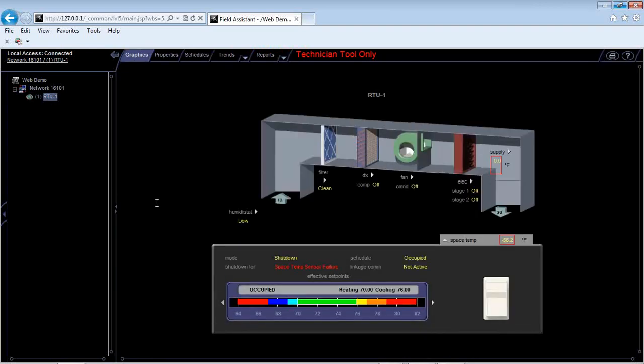Okay, so this is my view file. This is exactly what is going on with my controller, just kind of a general graphic status, right? So you can see I have a filter, a DX section, a fan, an electric heat exchanger, and then I've got some temperatures, okay? This is a brand new Carrier controller, okay? All of these rooftop controllers come standard with their RTU Open program on it. So all I did was upload this. I didn't add anything. I just hit upload, and this is what showed up right out of the box, okay? Now, we might not be controlling a unit that has DX cooling and electric heat, but it still comes standard on the program. That's something that we're going to configure, or we call program, for our specific application, okay?